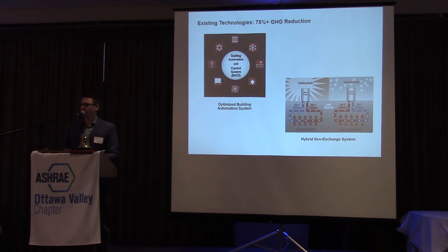What we're finding is that by doing a hybrid system, one that optimizes your base load of heating and cooling, and then handles peaks with traditional techniques like gas-fired boilers and cooling towers, you can get probably two-thirds to three-quarters of the savings you're looking for. That's really the sweet spot you need to find, otherwise it's just not cost-effective.